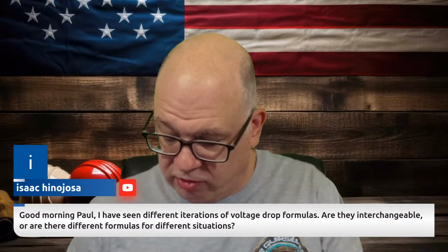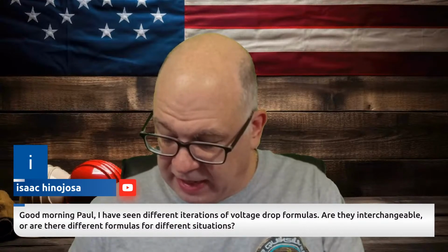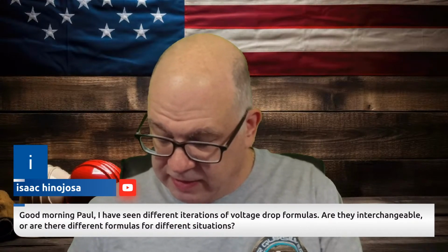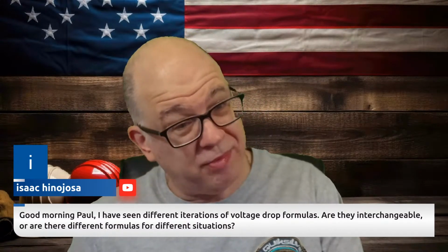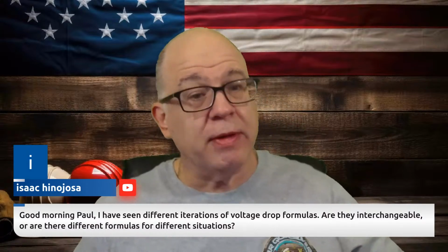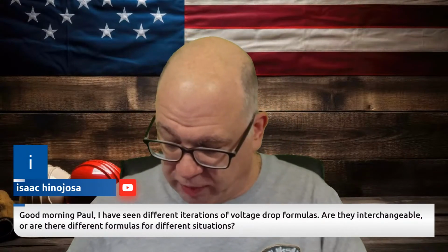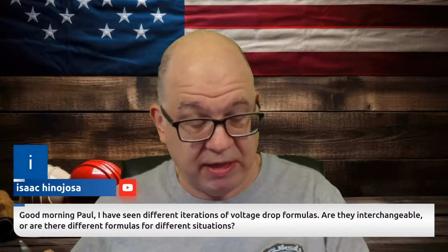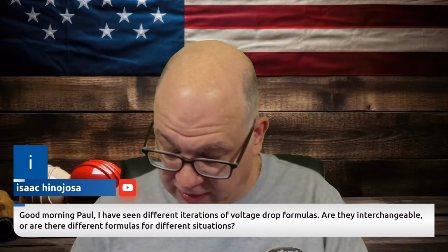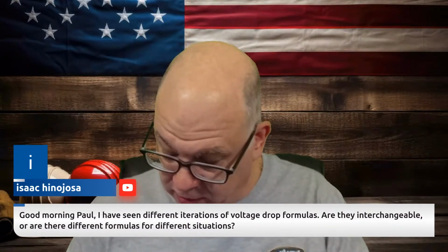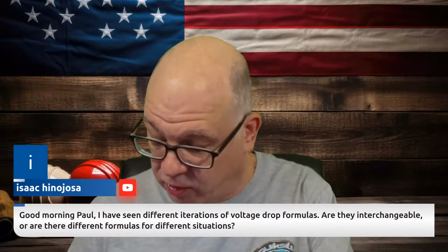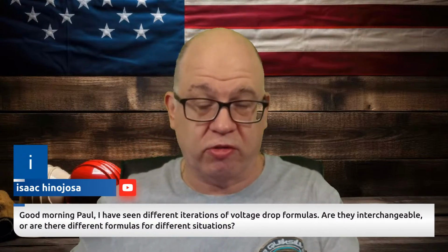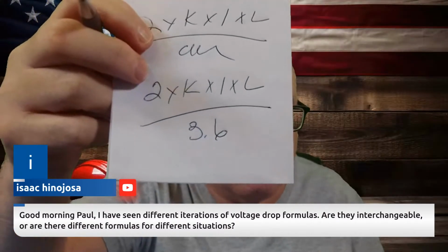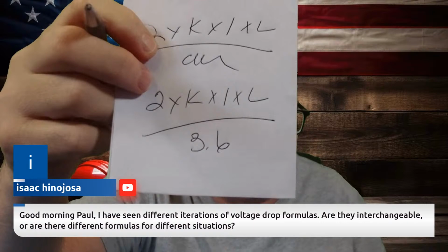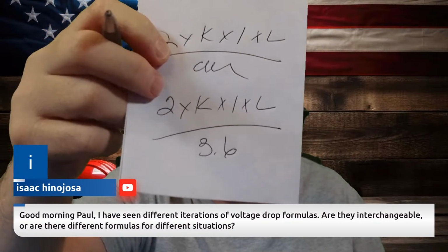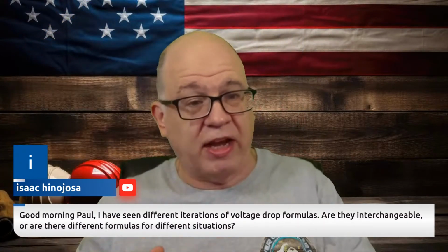Or you could do 2 times K times I times L divided by the actual voltage drop. For, let's say, a 3% voltage drop, if that's what you're doing for a branch circuit, right? So basically you're going to go, okay, it's 120, then you go times 3%, so that's 3.6 volts. That's what you're putting, the actual volts that drop. So then you've got that formula, 2 times K times I times L divided by the actual voltage drop will give you conductor sizings in circular mill.